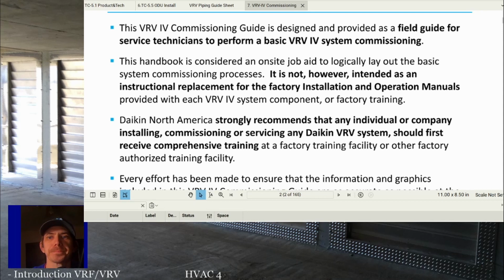Quick case in point, if you're working on a Daikin system, all the wiring is two wire, not shielded. Don't really have to worry about too much. It does require stranded wire, but it's not shielded or anything. Unless Carrier's changed anything in the last few years, Toshiba Carrier, then they require shielded wire grounded on one end for all their communication. So if you put in wiring like it's a Daikin system, and you don't have shielded wire that's grounded on one end, and something doesn't work, they're going to tell you it's because you installed it improperly, whether it would actually cause a problem with operation or not.